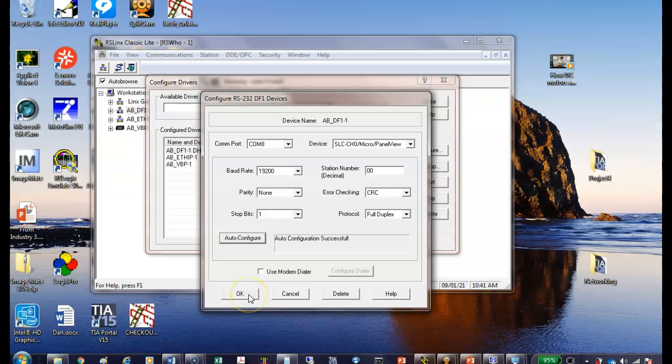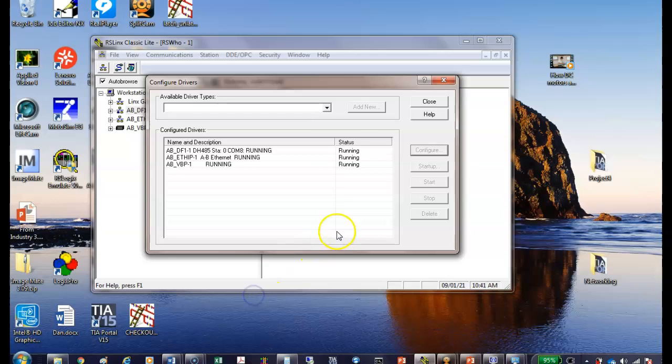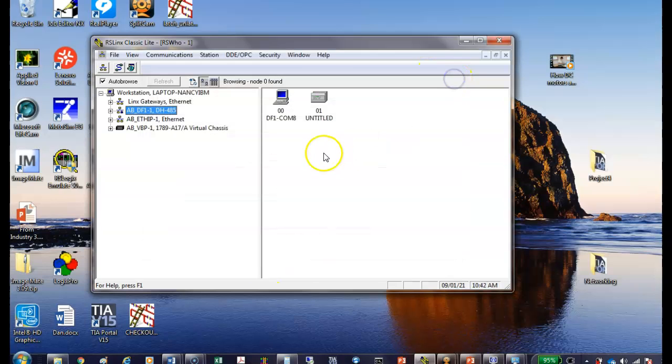So now when I go in and, so no, we're not using parity, but we know what parity is, right? So RSLinx. So if I go out and install a CompactLogix PLC, a brand new CompactLogix, the first thing I'm going to do is run RSLinx, and I'm going to load in the right driver, and then we're going to configure the driver, right? Now once we got the driver, so I'm going to come up here and click on that. There's my PLC right there. So I'm ready to go. I'm ready to go to work.